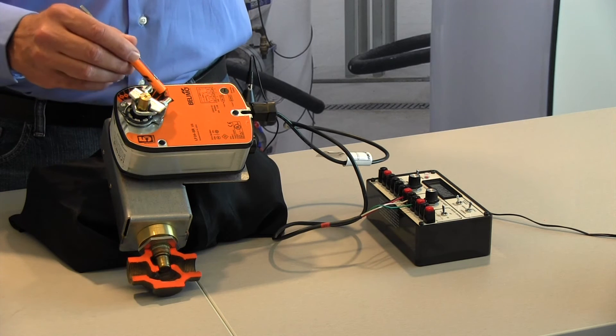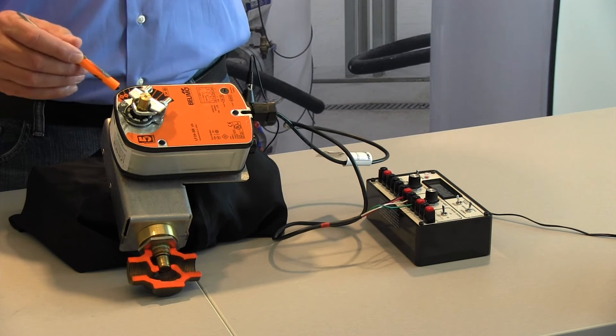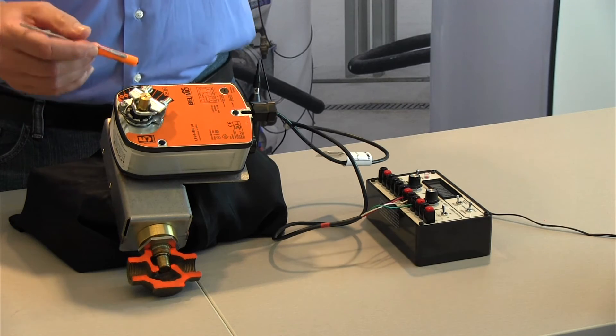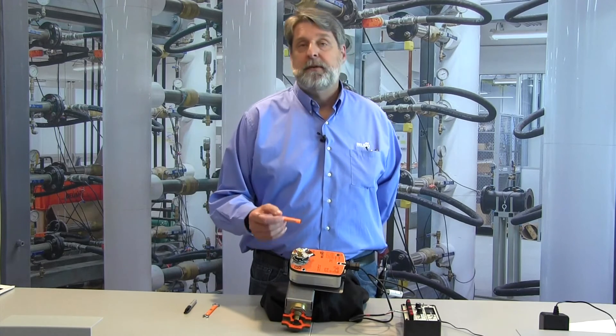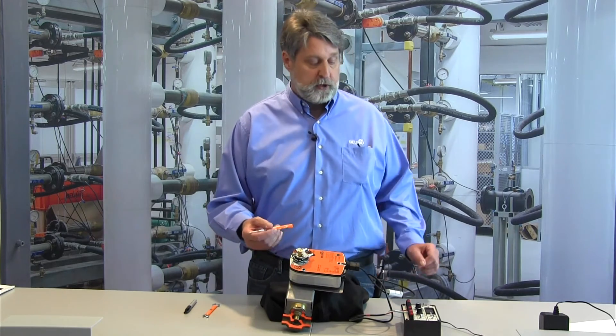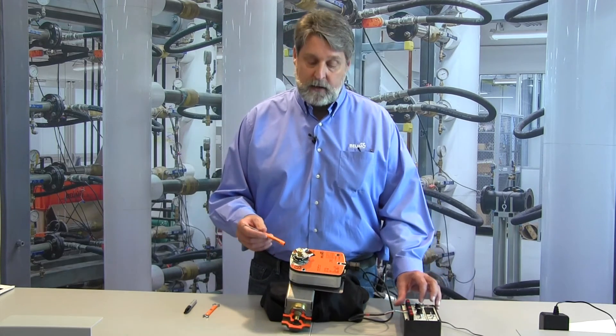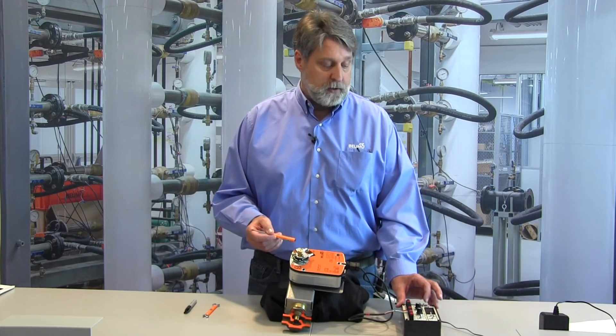We have a scale on the outside of the actuator and it's just for general reference. Because this is a spring return actuator and I've got it set up to fail in the fail close position, when I remove power the spring is going to drive the actuator closed.